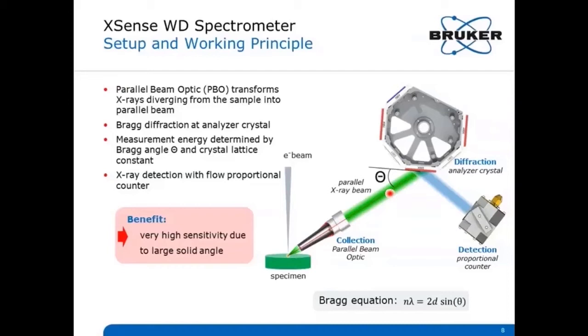The resulting parallel X-ray beam hits one of the flat crystals, where Bragg diffraction occurs. There are up to six crystals on the turret. Only photons of a certain energy fulfilling the Bragg conditions are reflected towards the proportional counter, which is used for X-ray detection.